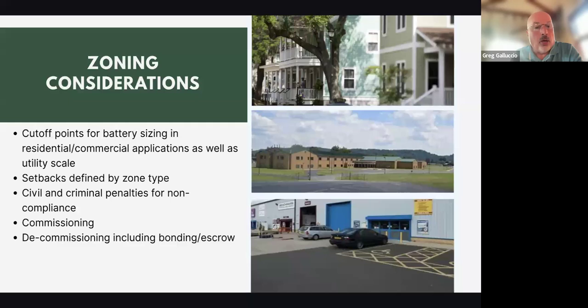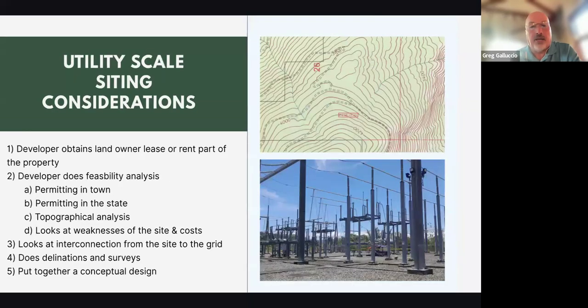This is really important: commissioning and decommissioning. You have control over this. Commissioning has to happen only after it's been ascertained that all of the permitting has been done correctly, that all of the safety requirements have been met and certified, and that all of the training needed, for example for first responders, has already taken place. You don't turn this thing on until we see all that. That did not happen in Warwick. It needs to happen everywhere, every day from now on.